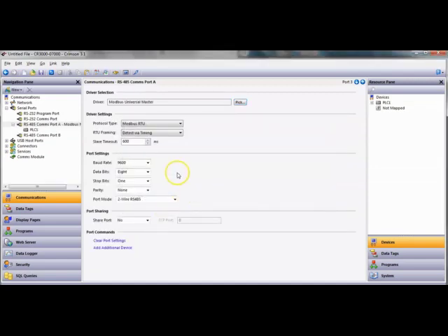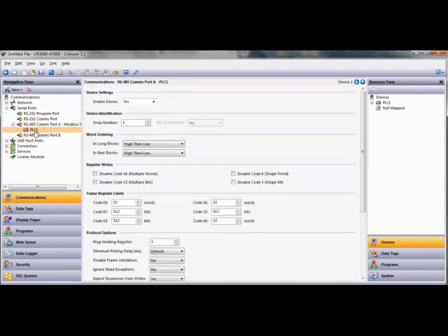We'll click OK. Notice I'm going to leave all the baud rate settings here at the default: 9600, 8, 1, and none. Two-wire Modbus RTU. Over here on the left, where it says PLC1, I think I'll rename this one, because this is actually going to be the device. So let's call it slave_port_B, because that's the device it's going to be talking to. Notice here the drop number is 1. I'm going to leave everything else here by default.